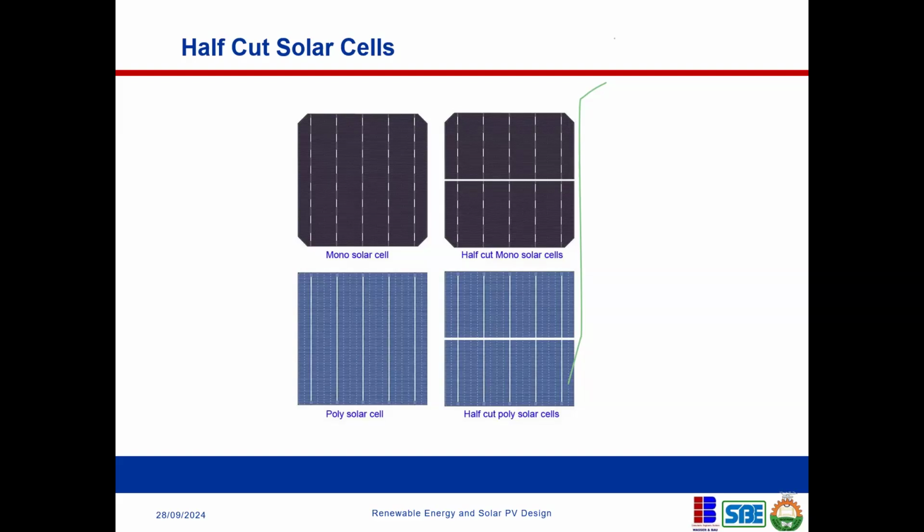For most of the recent technology that we have now, for the first year, degradation will be like 1%, okay? But the subsequent years are going to be 0.4%. Before now, we had 0.5% degradation every year. But now, technology has improved so much that for the first year you can have 1% degradation, and then for the subsequent years you have 0.4% degradation, okay? So if you do the mathematics, you find out that solar panels can last over 25 years, even going into 30 years, because of this improvement in technology.